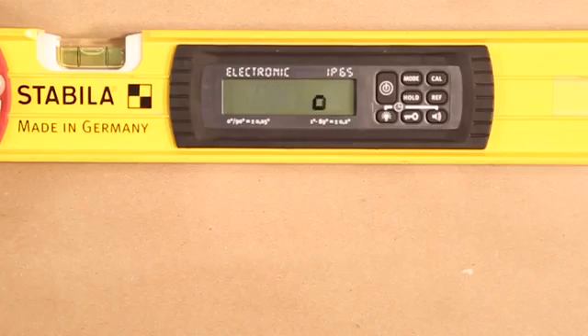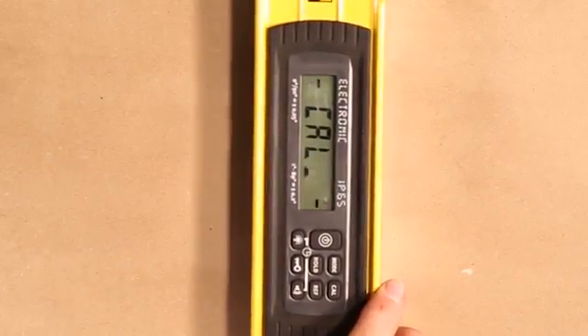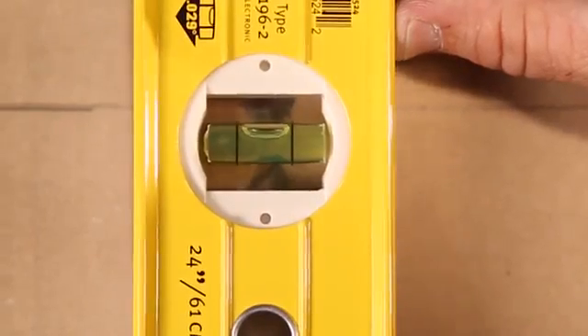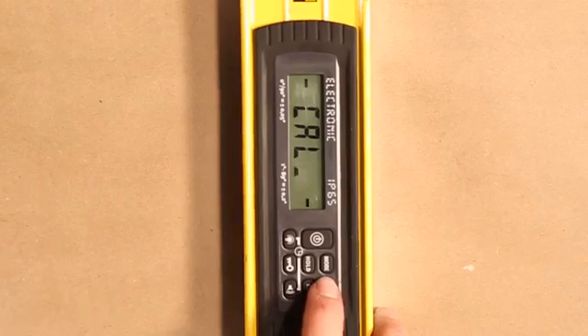You're going to notice the bottom line will stop flashing. That's when you do your first rotation. We're going to rotate counterclockwise. You're going to center your top vial. You want to get that perfect. Once that's done, you're going to hit calibration.